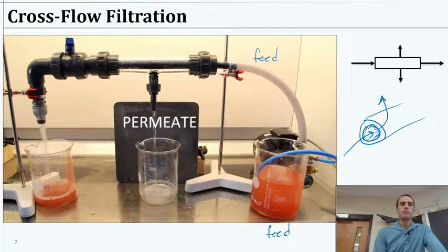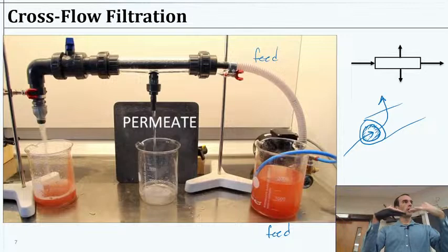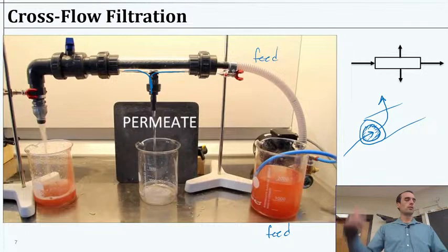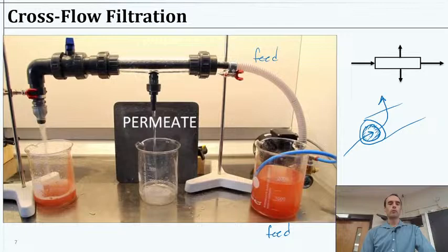And if you look closely, you can see there's sort of a plexiglass thing, and then this membrane is inside that, and it's collecting whatever water makes its way through. Once it gets out of the membrane, it'll drip down into this collection area, and that's where we're getting the permeate, right? So that's what's happening with the water. Now, the rest of the water that stayed inside the tube and didn't make its way through is being discharged through this side, and that would be the retentate.